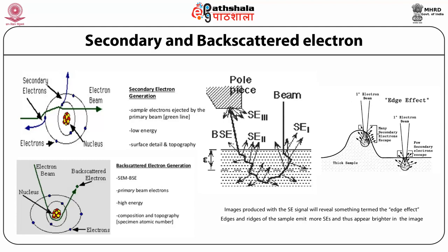Backscattered electrons are those electrons scattered backward and emitted out of the specimen. When incident electrons are scattered in the specimen, they are sometimes called reflected electrons. Since backscattered electrons possess higher energy than secondary electrons, information from relatively deep regions is contained in the backscattered signal. Backscattered electrons are sensitive to the composition of the sample — the larger the atomic number of the constituent atoms, the larger the backscattered electron yield. An area consisting of heavier atoms appears brighter in the backscattered electron image, making it suitable for observing compositional differences.